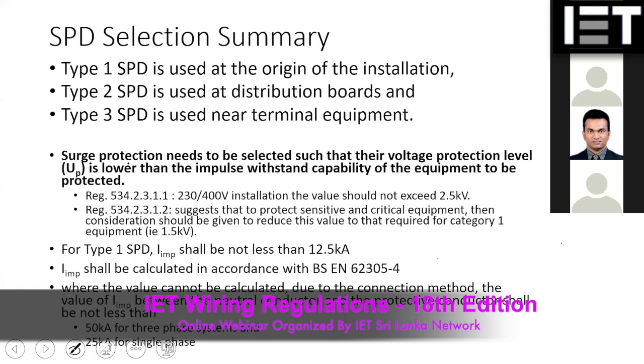And also there are a few other requirements in the low voltage application. Your voltage protection level should not exceed 2.5 kilovolts. That is a mandatory requirement. For the critical equipment, those are considered category 1 equipment, your UP value should not be more than the insulation level. Generally, our insulation level is UW, and when you are selecting your UP value, it should be less than or equal to 0.8 times UW.